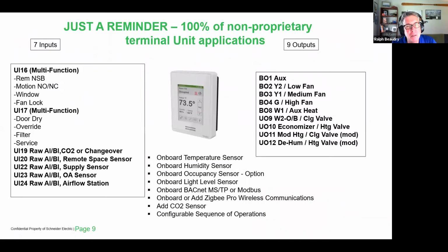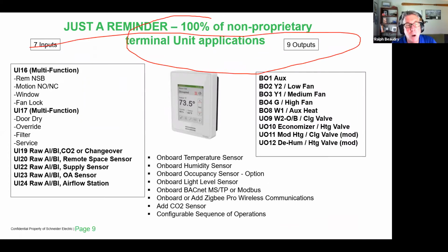So on the 8000 there's a bunch of I/O. We can do 100% of non-proprietary terminal unit applications with this, because we've got 7 inputs available. There's 7, and this is recent, they're now all universal inputs, so they're either binary or analog inputs. UI 16 and 17 are multifunction, meaning you can select different applications, like whether it's a window input or fan lockout input. Input 17 is door contacts, filter, service alarms.